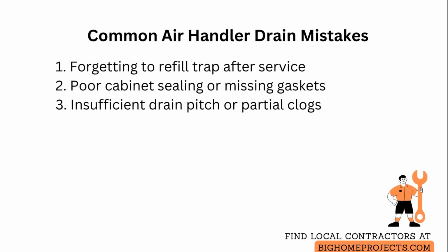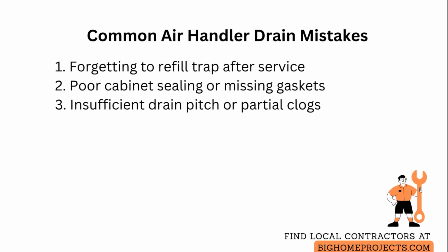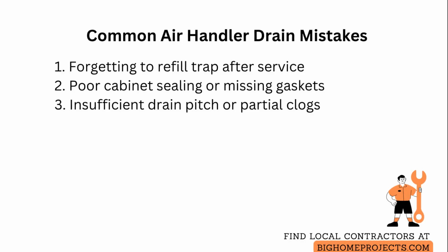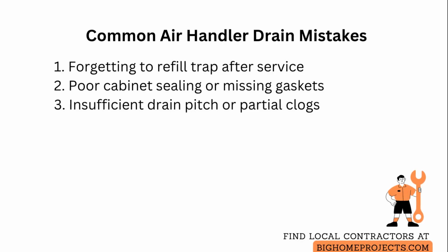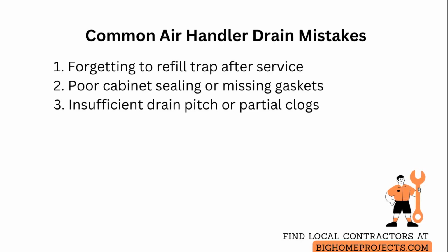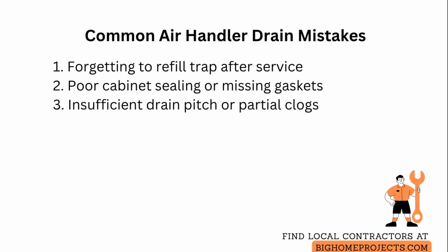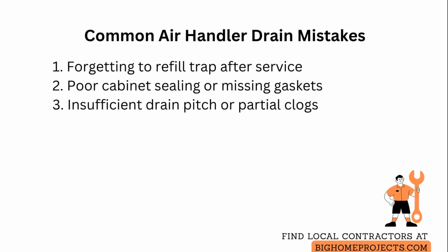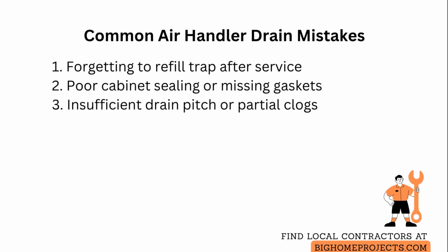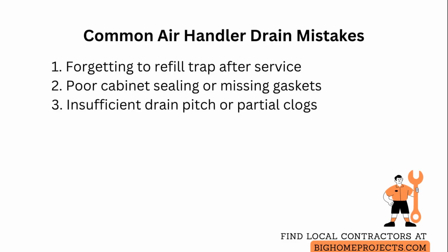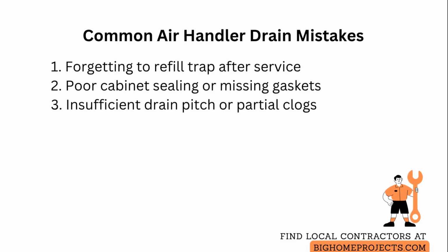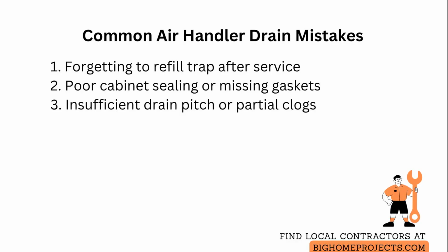Common mistakes include forgetting to refill the trap after service, which allows outside air to be sucked through the line. Always pour enough water to re-establish the seal and verify it holds. Another issue is poor cabinet sealing or missing gaskets that create internal negative zones. Reseat panels and replace damaged gaskets to restore proper pressure balance.